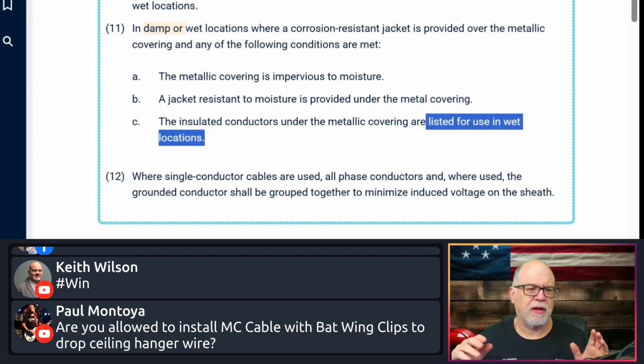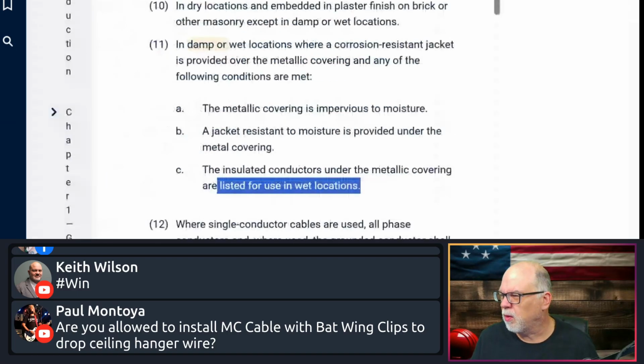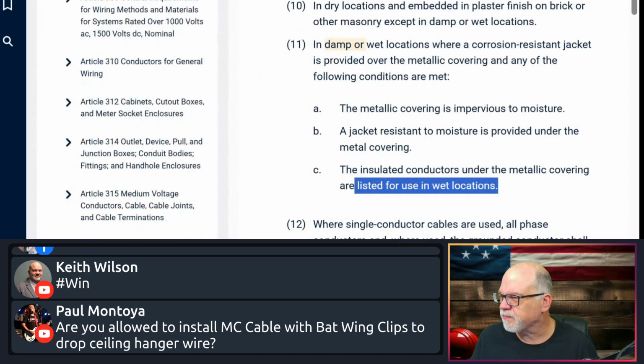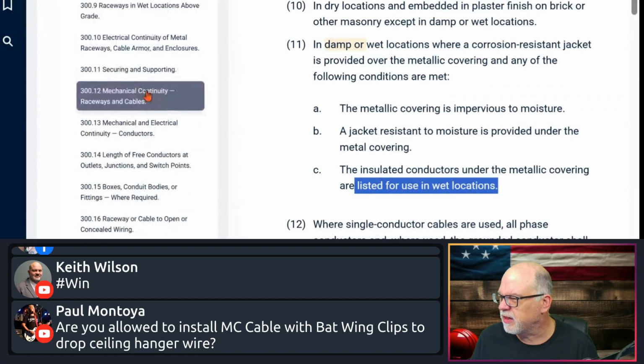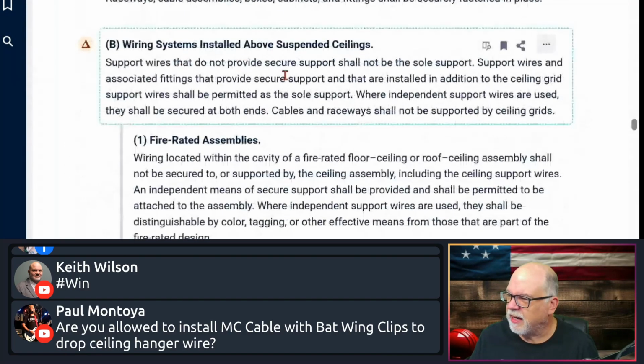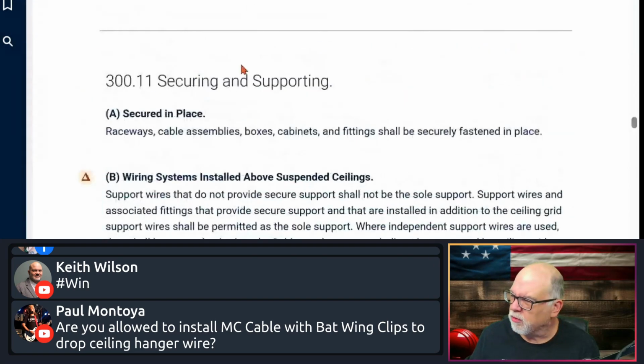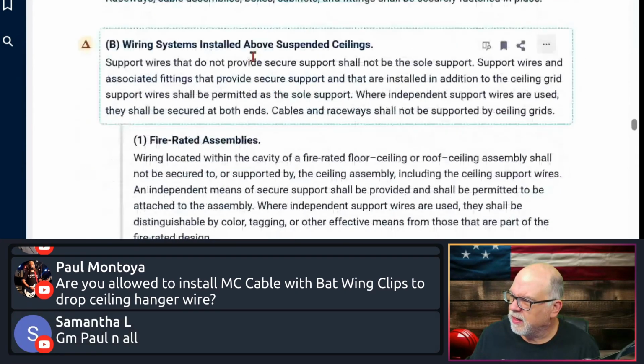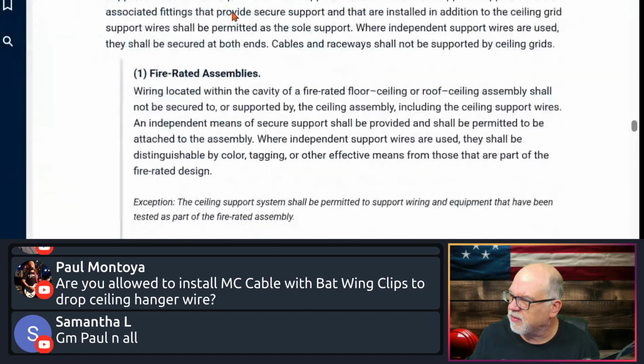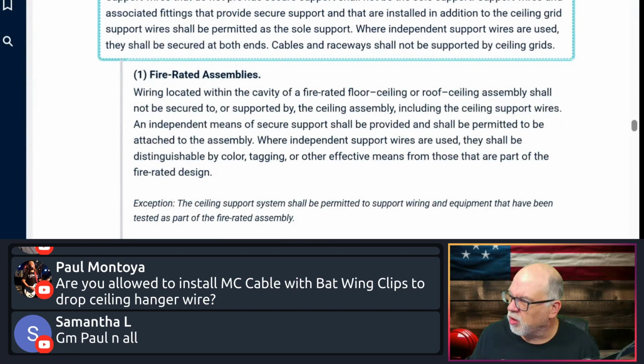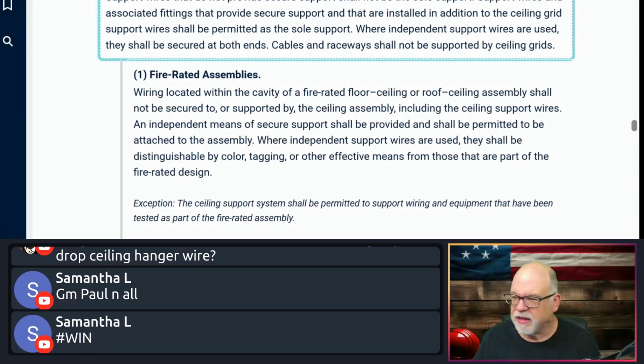Paul says you're allowed to install MC cable with batwing clips to drop ceiling hanger wires. Not if they're designed to support the ceiling. You have to have your own separate requirement for that, right? And so, Paul, where we would see that, if you want to go review that, is going to be at 300.11 right here. So this is where you're going to look, Paul, if you want to review that: securing and supporting cable assemblies, that type of thing. It says wiring systems installed above a suspended ceiling, which sounds like what you're doing with your batwing application, right?